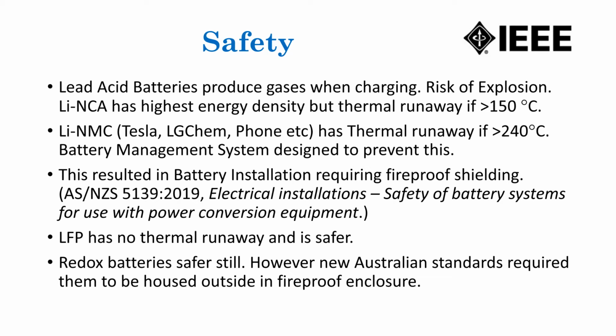Flow batteries are safer still, but the new Australian standard says anything that's not a lithium-ion battery has to be housed outside in a fireproof enclosure. So flow batteries that can't catch fire have to be installed in a fireproof enclosure. The standards are a bit crazy.